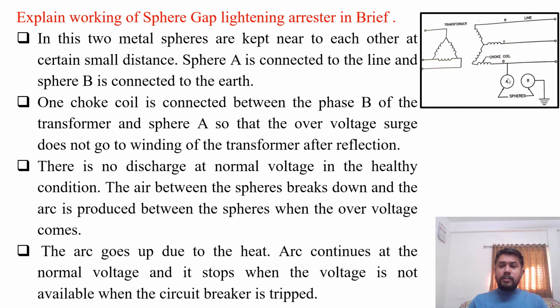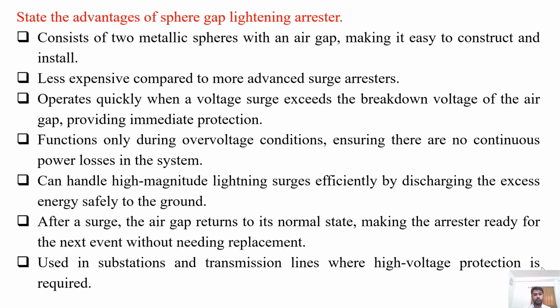There is no discharge at normal voltage in the healthy condition. The air between the spheres breaks down and the arc is produced between these spheres when the overvoltage occurs. The arc continues at the normal voltage and it stops when the voltage is not available, when the circuit breaker is tripped. So without the tripping of the circuit breaker, the arc does not quench in this type of arrestor. State the advantages of sphere gap lightning arrestor.